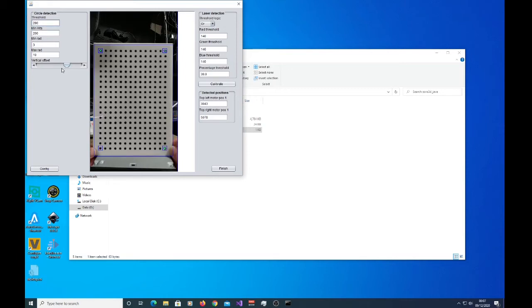Close. I think if I adjust the... Oh, there we go. We had 4 dots there. Okay, so it's not precisely on. It's as close as we're going to get it. And at this point, I'm going to reduce the green threshold. So this is the pixel value detector, and the green content needs to be higher than this number for it to be considered a detected spot.